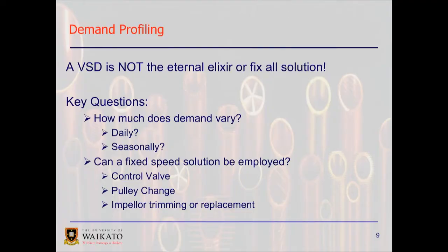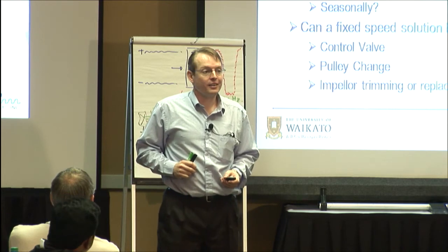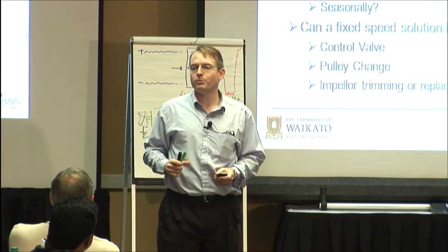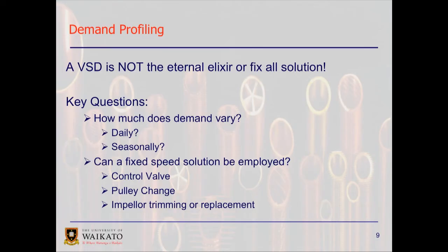A VSD is not the eternal elixir or fix-all solution. You've got to ask a couple of key questions. Number one, how much does the demand vary? Daily, seasonally? Who mentioned that your grain elevators might be up and down, so the load could be varying? Now, the question you've got to ask yourself is, can a fixed speed solution be employed? A pulley change, an impeller change on a pump or a fan?